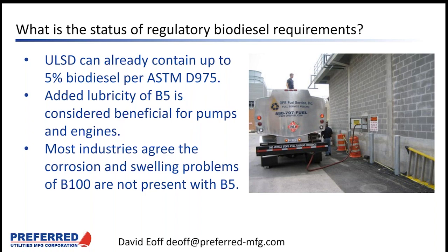Ultra low sulfur diesel has lower lubricity than low sulfur diesel. So part of the reason to blend in some biodiesel is to restore the lubricity lost when diesel was mandated to become ultra low sulfur diesel. B5 is very common, and most industries have not seen a problem with corrosion or swelling of seals related to B5. Preferred burner and fuel system technicians aren't seeing issues with customers using B5 either.